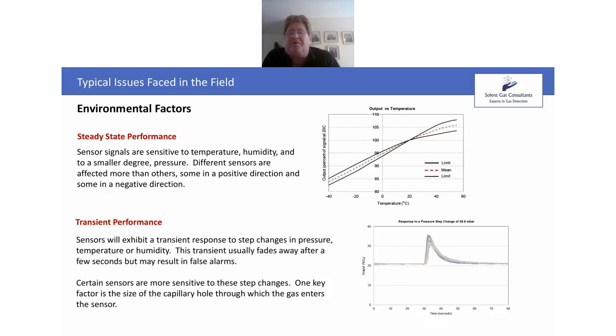This is often a problem when you're using pumps to pump the gas over the sensor. Pumps often use a chain of pulses, or pressure pulses, which will result in a chain of these transient spikes, which can then be read as a high signal. So care needs to be taken to design the gas delivery system when using pumps to make sure that the pressure pulses from the pump don't interfere with the sensor.